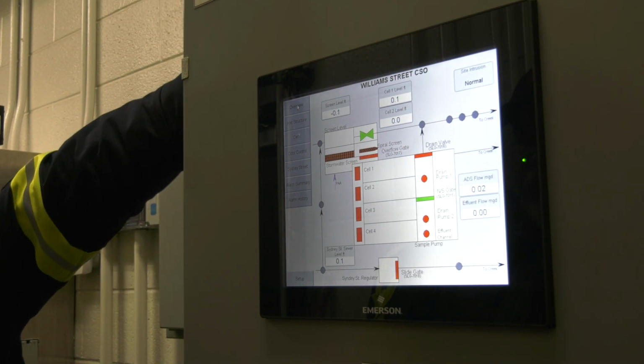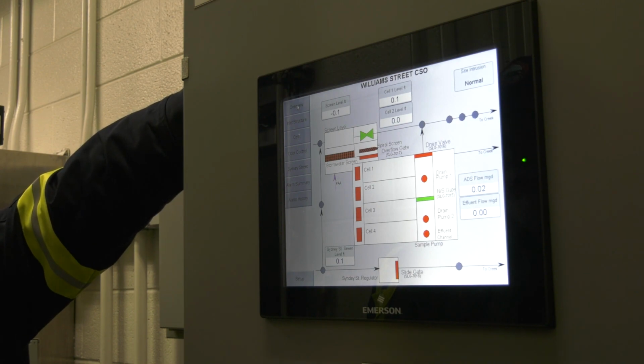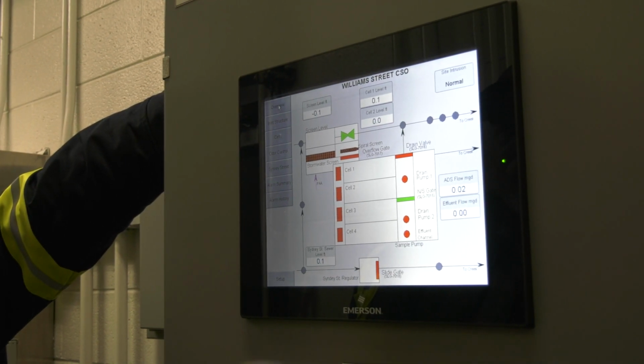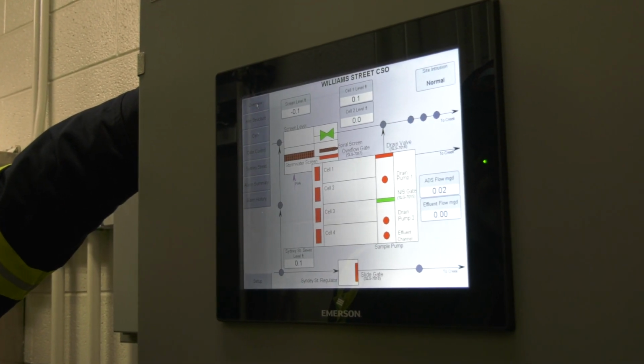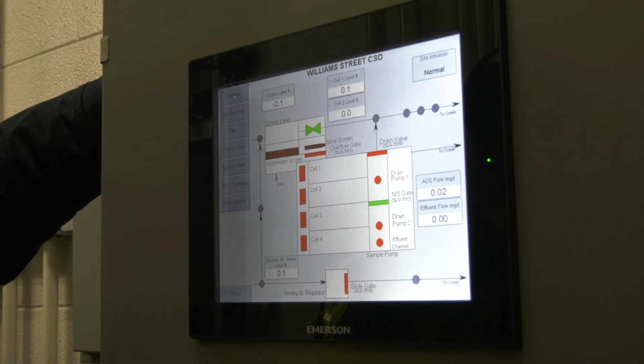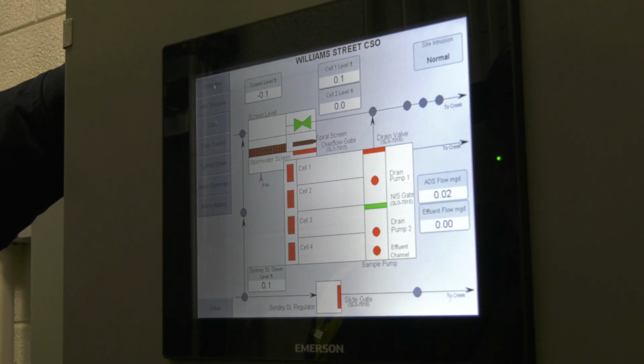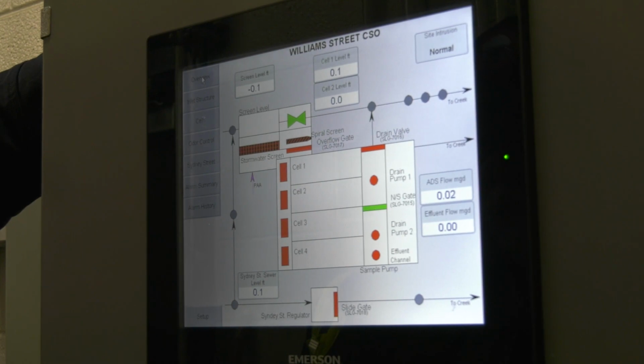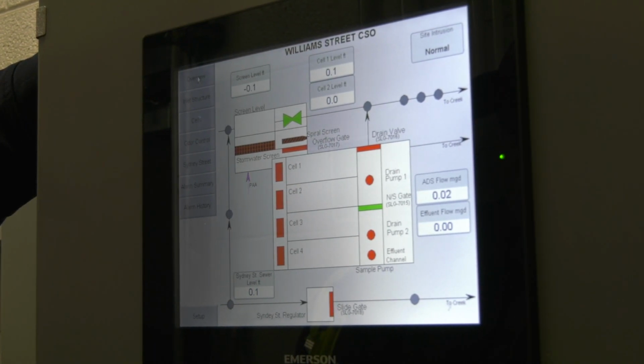All right, so facility activation. When the Sydney Street gate is not closed, and there's a limit switch here to show when the gate's open or closed, the inlet valve position command will be set to 20 milliamps. So the CSO inlet gate will be 100% open. Then we'll wait 2 minutes. And when the Sydney Street level gets above the operator adjustable set point, we'll set the inlet valve position based off the level at Sydney Street. The valve position command will be updated at an interval defined by the influent gate adjustment delay set point.